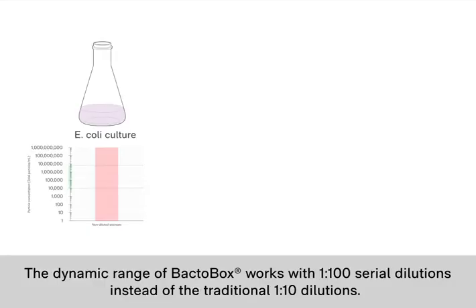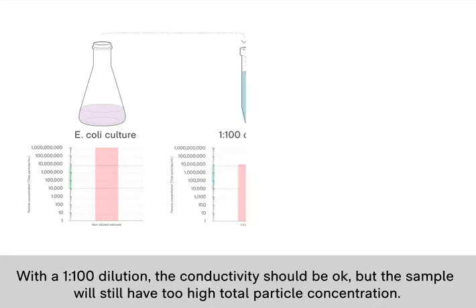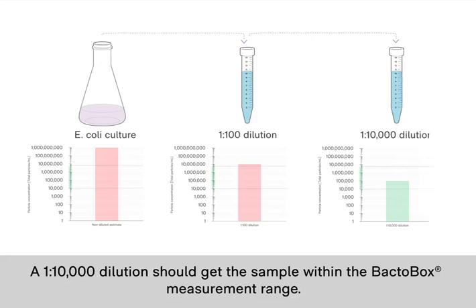The dynamic range of the BactoBox can handle jumps in steps of 1 to 100 dilutions instead of the 1 to 10 dilutions that we traditionally use in microbiology. Now if we do a 1 to 100 dilution, the conductivity should be okay but the sample will still have too high total particle concentration. Instead, a 1 to 10,000 dilution should get the sample within the BactoBox measurement range.